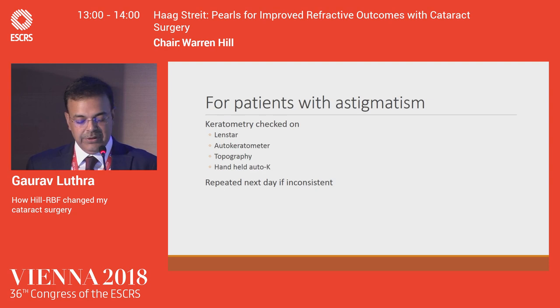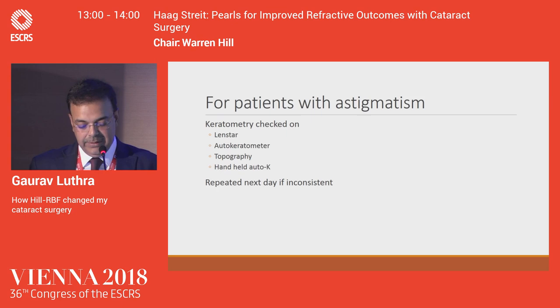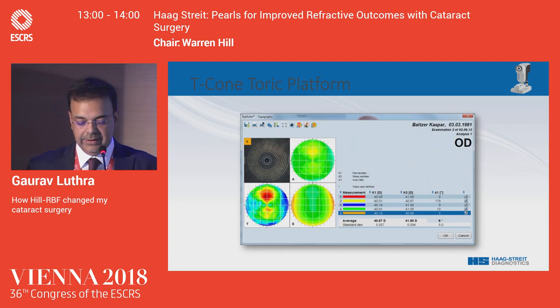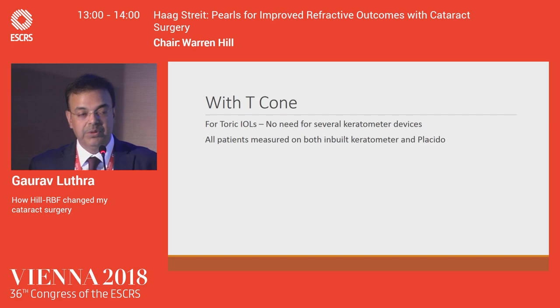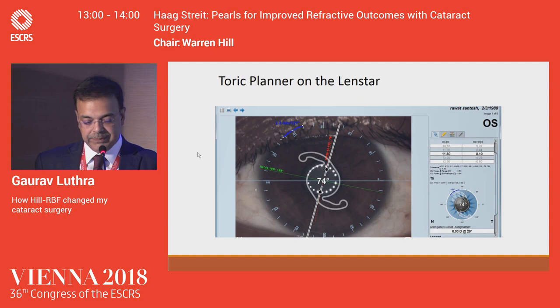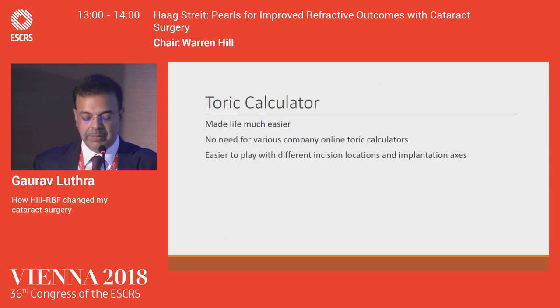With astigmatism, we continued to use all other methods of measuring — as Warren repeatedly says, you have a primary method and a secondary method. I have three methods for almost everything and several ways to check all my results. Then came the T-cone on the LENSTAR. This made a huge difference because now we had a more efficient placido-based topographer. For our torics, we had this option where we could see the bowtie and find the reliable axis, so we cut down on the number of ways we would do keratometry. We would do both the T-cone and another method, and for the axis I would look at the placidograph and decide whether I wanted to use that axis. The toric planner was also very useful — we no longer had to go to various company websites for online calculators. We had everything on the machine itself.